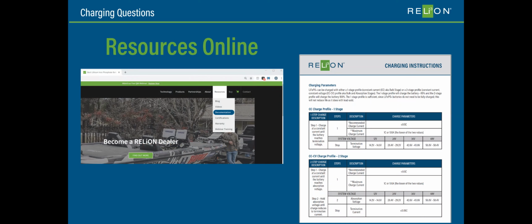I don't want to go into too much detail, I'll let you read it, but one thing we'll be touching on repeatedly is that we recommend a 0.5C charge, although you can charge up to 1C. The voltage range you're looking for to charge the battery is 14.4 to 14.6 on a 12-volt basis, and you just increase that incrementally with the proper multiplier for larger voltage systems.